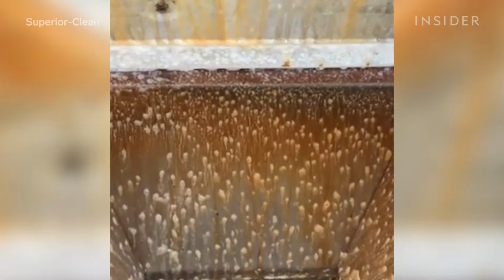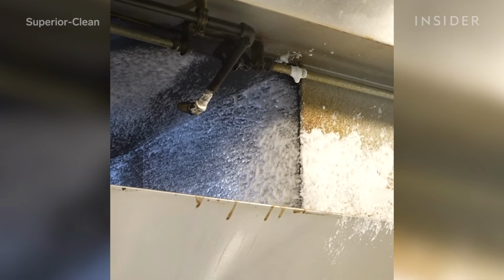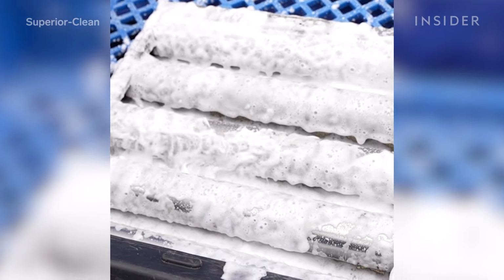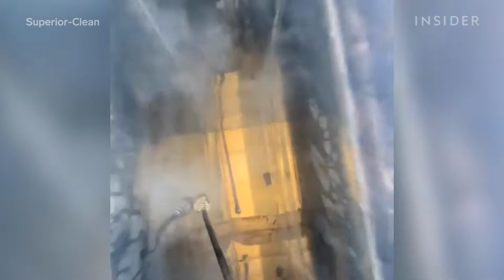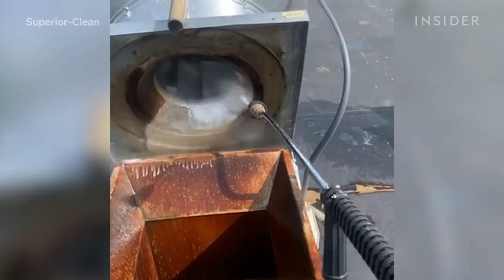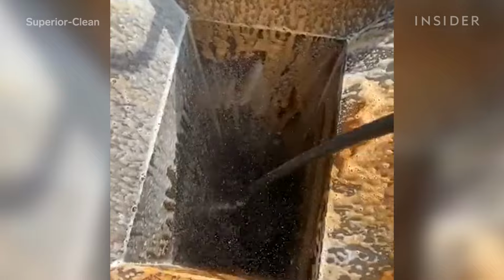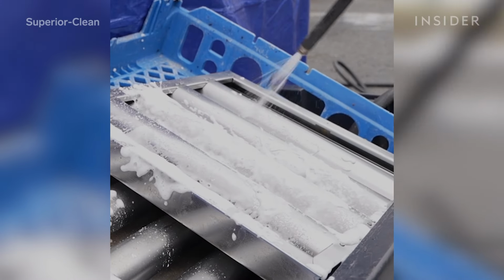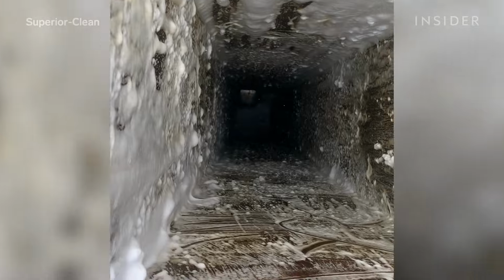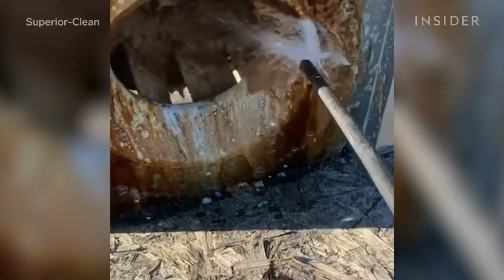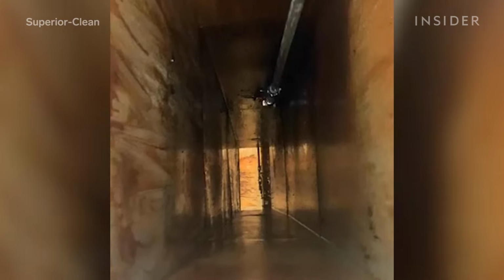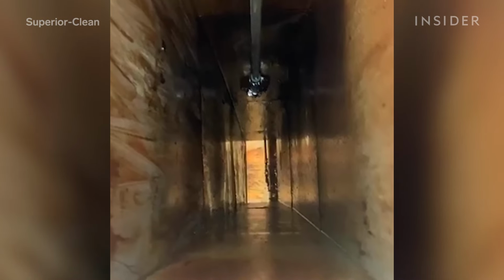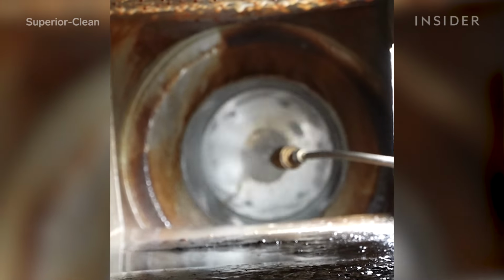The purpose of cleaning the upper ductwork first is to ensure that we properly flush the entire ductwork back into the kitchen hood. So our goal as a certified hood cleaning company is to ensure that all accessible areas of the hood and ductwork are bare metal, meaning there is no grease left over and there's no possibility of a kitchen fire. So the way we start degreasing the system is with a high foaming agent, and we can mix in sodium or potassium hydroxide to strengthen up our mix. From there, we will scrape down the ductwork to ensure that all the thick grease is removed before we come back and hit it with high pressure steam cleaning.